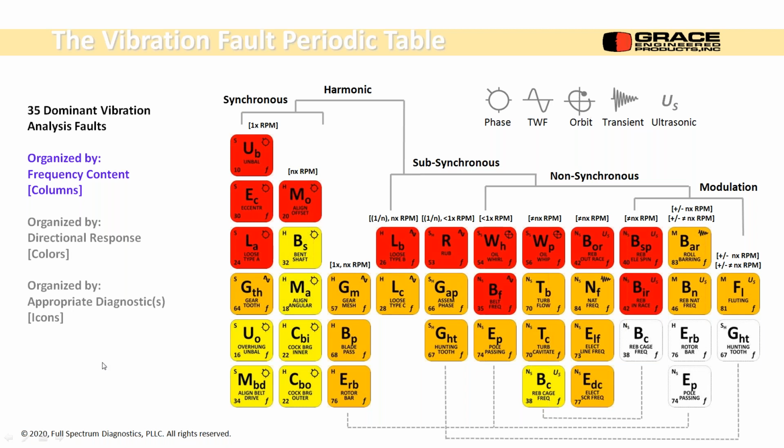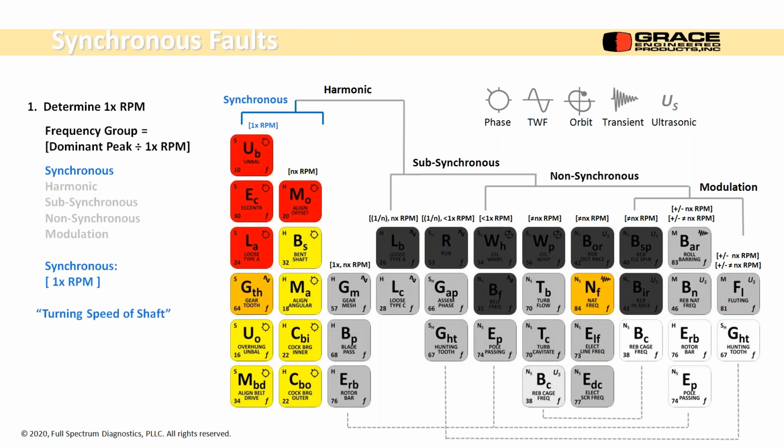This is exactly what I've just said to you. It's a synchronous problem. It's in the radial direction. It's one of these 4. We do a phase analysis and we weed out which one is the oddball in here, and we're to our solution. Yeah. Pretty much as simple as that. But life throws you curveballs every once in a while, like every week for me. We're going to look at synchronous faults.